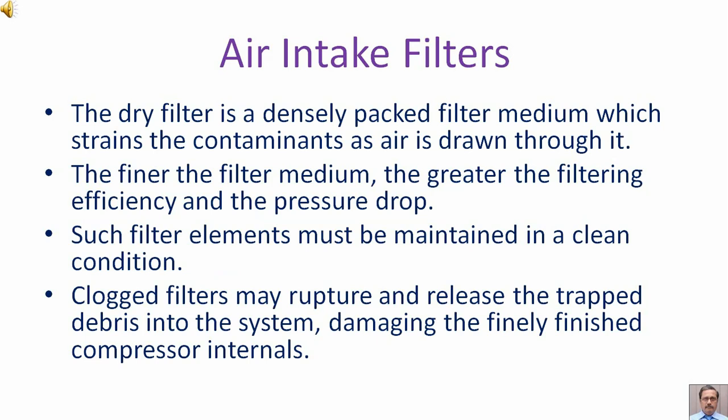The dry filter is a densely packed filter medium which strains contaminants as air is drawn through it. The finer the filter medium, the greater the filtering efficiency and the pressure drop. Such filter elements must be maintained in a clean condition. Clogged filters may rupture and release trapped debris into the system, damaging the finely finished compressor internals.